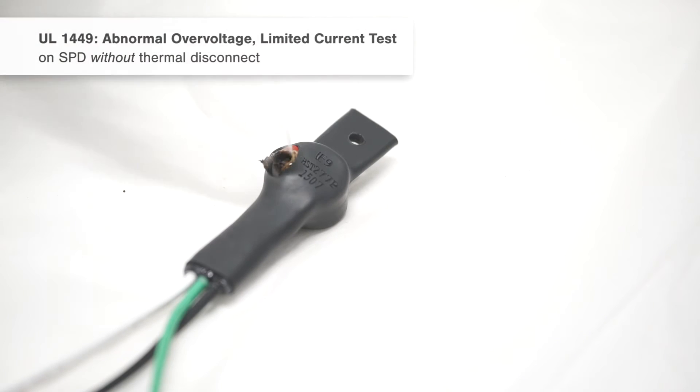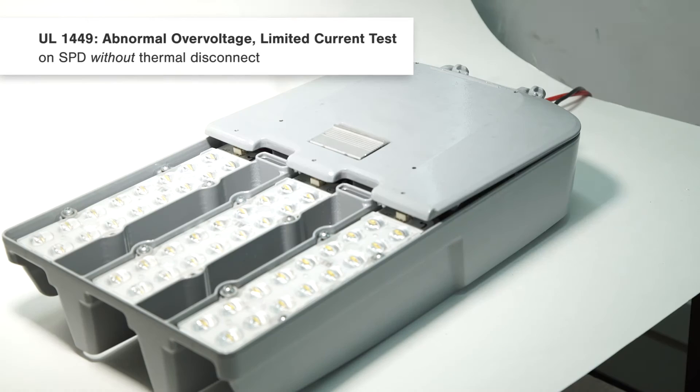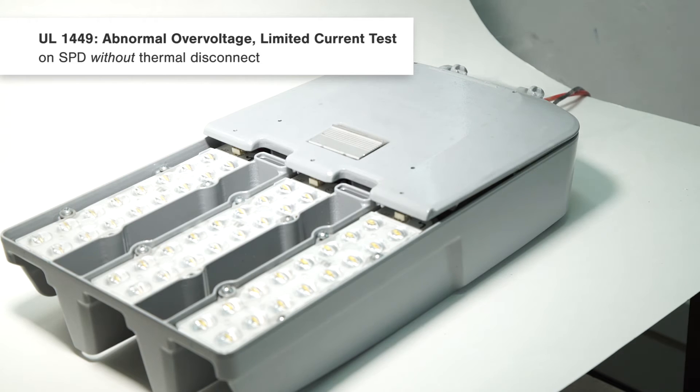Traditional surge protection devices, or SPDs, often lack thermal protections. When an SPD reaches its end of life or is exposed to continuous AC overvoltage, MOVs can overheat and begin to smoke, burn, and endanger the luminaire.